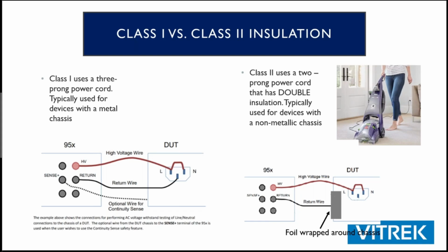Where it gets much more complicated is when you have that double insulated product. Now the user is potentially the path to ground. So you have to replicate where the user could touch. Sometimes this means wrapping it in foil, submerging it in water. With a photovoltaic panel, it's pretty standard to put the whole thing in a dunk tank, except for the leads. You're going to put high voltage on those leads and make sure that you're not getting any leakage into the water. That usually has some soap or something added to it to make it a little more conductive. So it's a little bit more complicated. The fixturing is a little bit more complicated, and every application is going to be a little bit different. It's a little harder for us to provide an out-of-the-box solution for class 2 products.